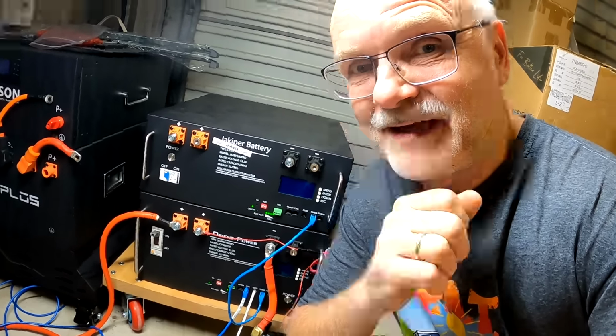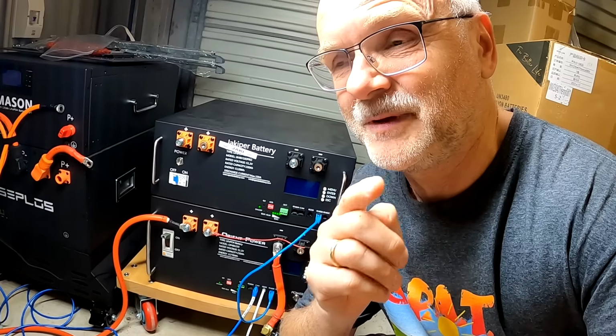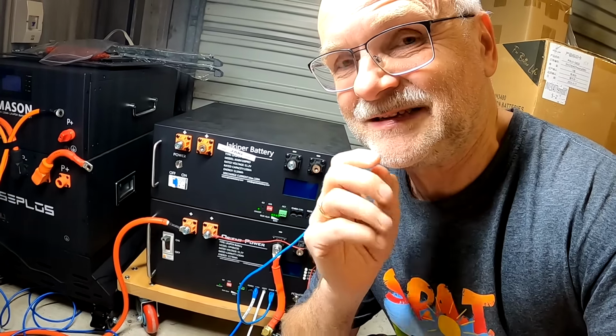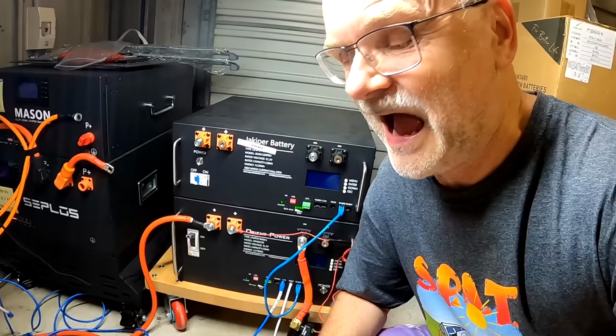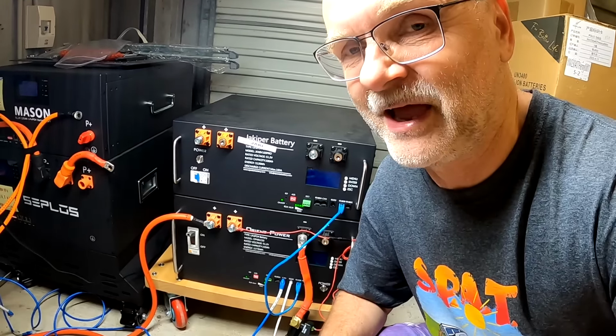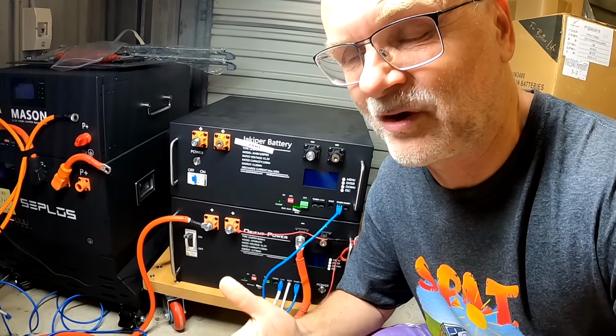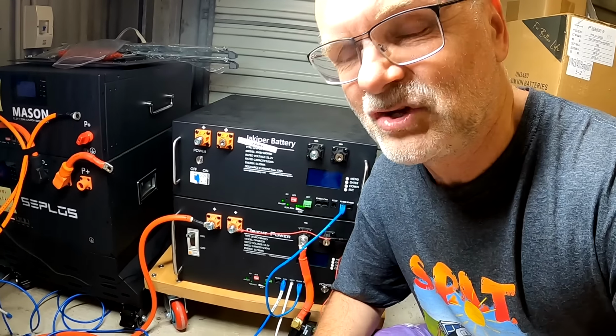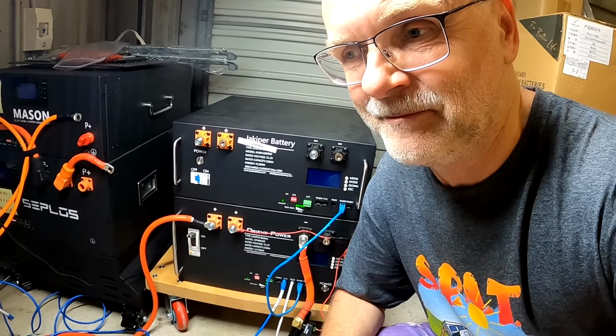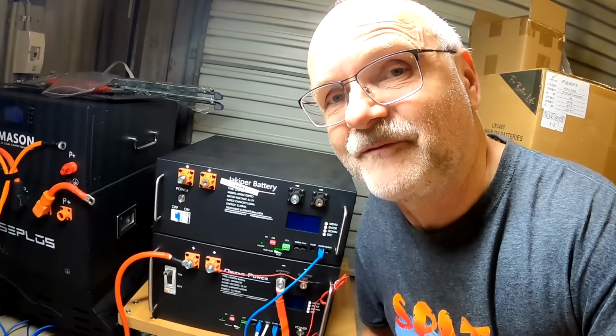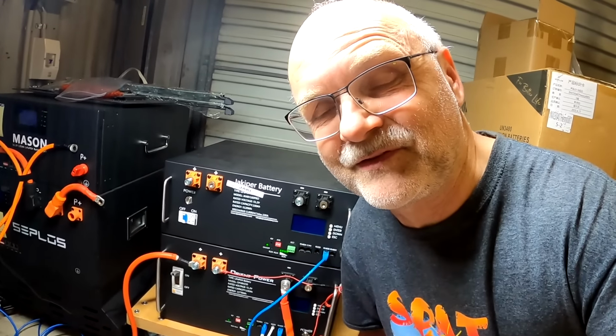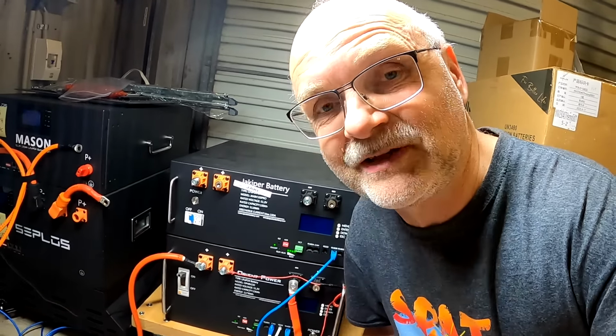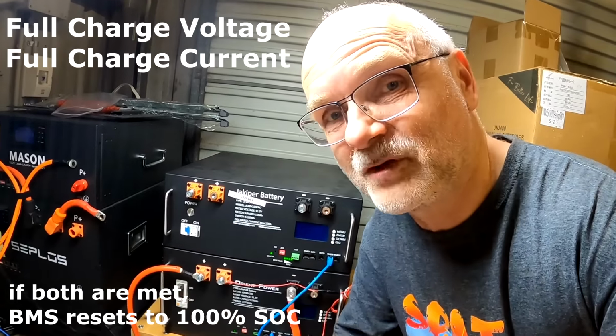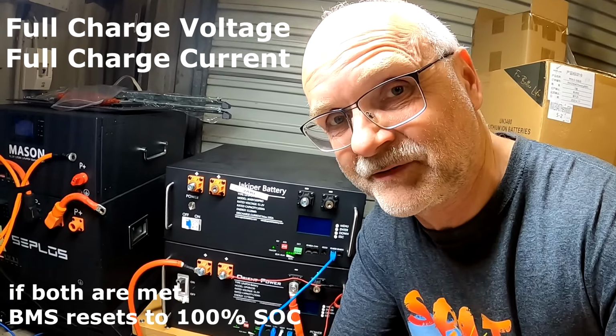So this would pretty much be the only negative point of this BMS, as well as the fact it doesn't have Bluetooth. I would really like to see a Bluetooth application for this BMS so I can quickly check it on my mobile phone and change a parameter here and there, without having any cables and adapters connected to my computer. A big advantage of the Pace BMS is that we can actually set a charge voltage and a tail current independent of the overvoltage protection parameters.